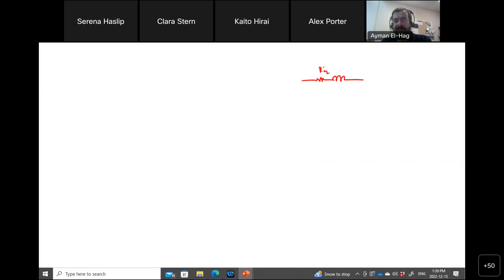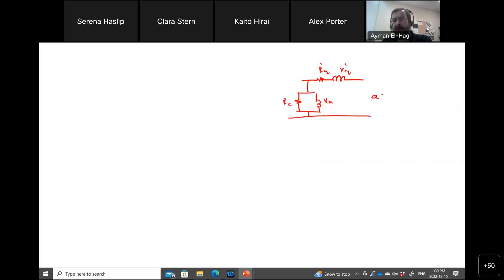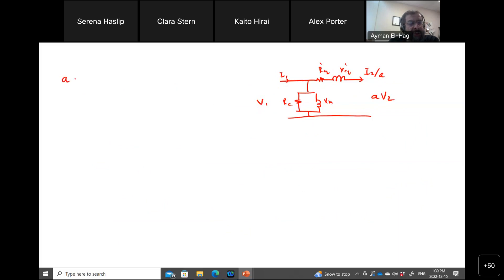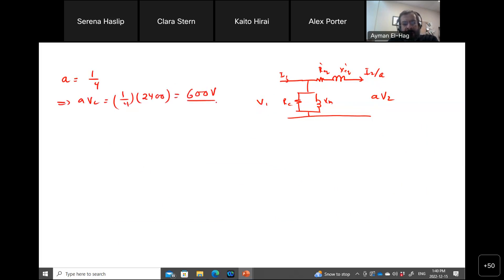Let me draw the model. We have R_eq', X_eq', and the shunt branch with Rc and Xm. This is referred to the primary, so the secondary voltage becomes A·V2 and the secondary current becomes I2/A. Here is V1 as input. The turns ratio a equals 1/4, so A·V2 equals (1/4) times 2400, which gives 600 volts. So the voltage at the output referred to primary is 600 volts at angle 0.